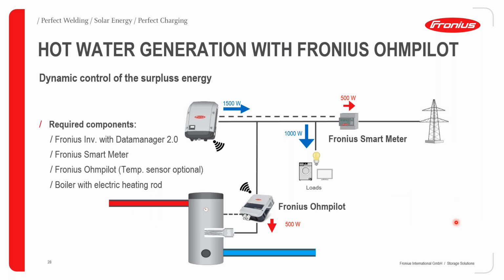A very basic overview of how the Ohmpilot works in a system. We have a Fronius inverter, which can be a Snap inverter or the Gen 24 Plus as well. We then have a Fronius smart meter in the system, and alongside we have also installed a Fronius Ohmpilot. Previously we were producing 1,500 watts of energy from the Fronius inverter. 1,000 watts was being drawn and sent to the load, whereas 500 watts was being sent to the grid. In some cases we can't even feed power to the grid, so the inverter would actually throttle down to 1,000 watts. In order to prevent the inverter from throttling down too much throughout the day, we can install an Ohmpilot, which will take that 500 watts, which was going to be sent to the grid if feeding limits were allowed, or which was going to be throttled down. We send that 500 watts to the Ohmpilot, and now we can increase the self-consumption rate of the installation.